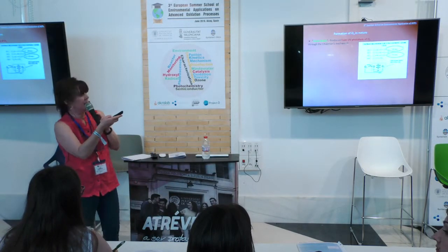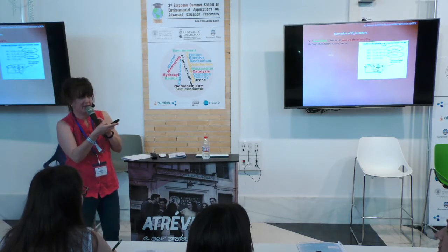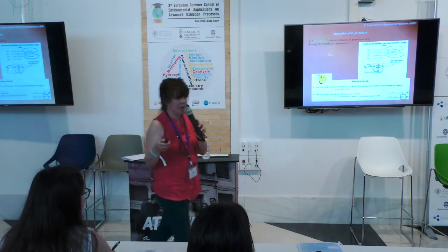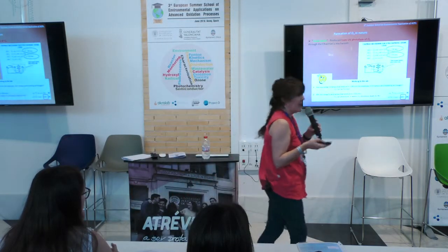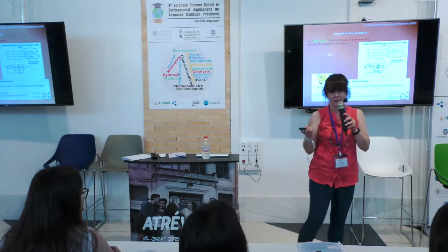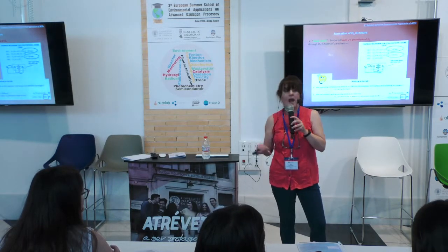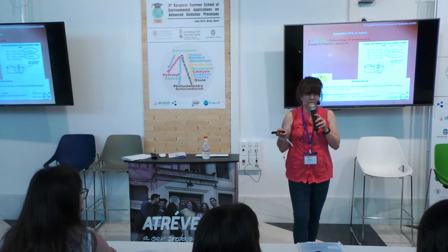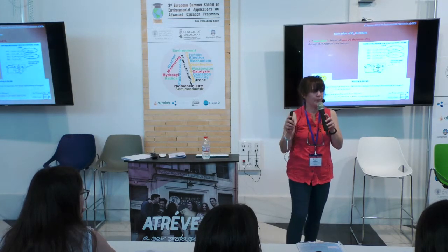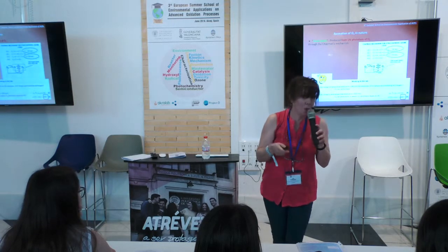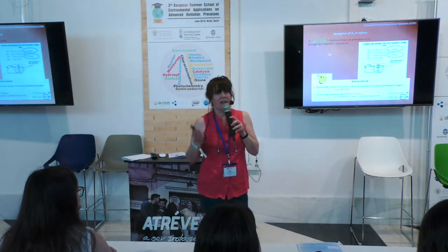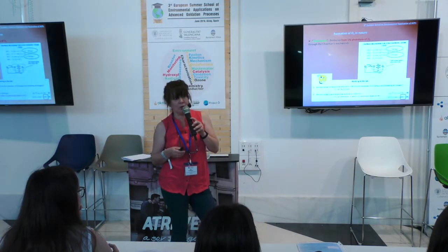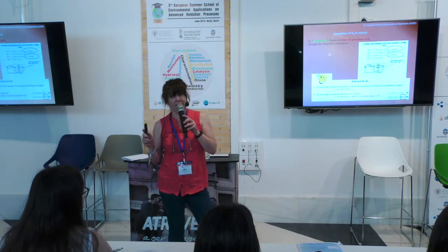Let's see these wavelengths that we have indicated here. If you are working with lamps that emit at wavelengths lower than 240 nanometers, such as vacuum UV lamps, and you are feeding air or oxygen, you can produce ozone. Take that into account. And if you are working with ozone and lamps that emit at wavelengths lower than 320 nanometers, you can photolyze ozone with formation of atomic oxygen.